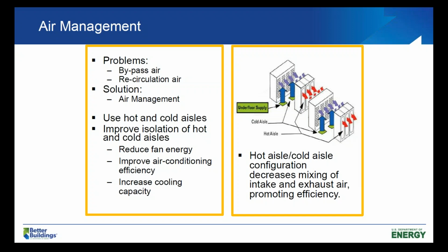So the very first step is using hot and cold aisles. As the right side of the slide shows, the blue arrows are the cool air coming up through the floor. The red arrows are the hot air coming out of the IT, out of the computing equipment, and those aisles alternate so that you have cool air coming up and going into both racks and then coming out of alternate sides of the racks to form a hot and cold aisle arrangement.